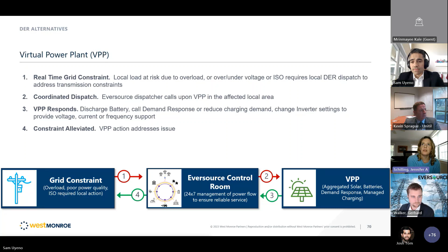In terms of the concept of virtual power plants, it's a very similar concept. I'll touch on this briefly: our control room needs to see what's going on the system in real time, and then be able to communicate with any type of aggregated behind-the-meter or large scale front-of-the-meter resource that can respond. Our control room can see it and address the grid constraint. This is what we call a virtual power plant, the terminology for taking all of these resources aggregated in a physical location at a specific point in time and bringing them to bear to address some constraint on the distribution system.